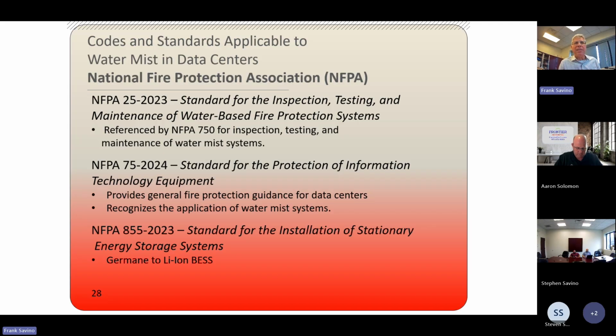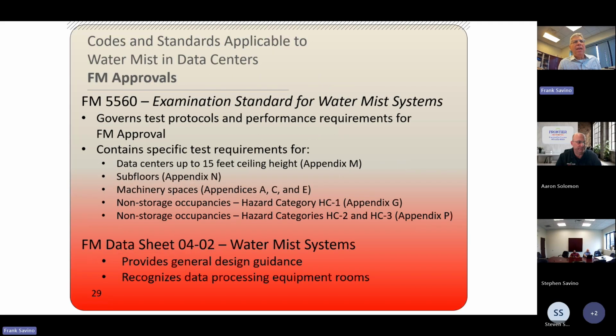NFPA 75, a standard for protection of information technology equipment, has very general fire protection guidance for data centers, but it does recognize water mist as an acceptable solution. NFPA 855 is a standard for the installation of stationary energy storage systems. And that's applicable to lithium-ion energy storage systems. Additional standards are FM 5560. That's really the Bible, FM 5560.